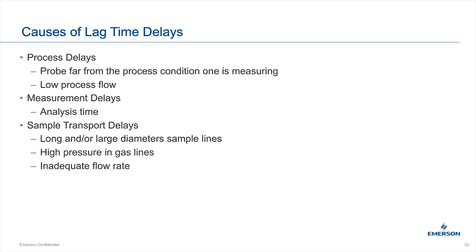There are several types of time delays in a system. One that people overlook is the process delay: if your probe is several yards from the end of your process, it takes time for the fluid from that process to reach the probe. That delay can't be made up downstream. In chemical applications especially, a low-flow liquid can make this even longer. Sometimes you can't place the probe right at the process because of high temperatures, so understand that placing it further downstream adds analysis time.